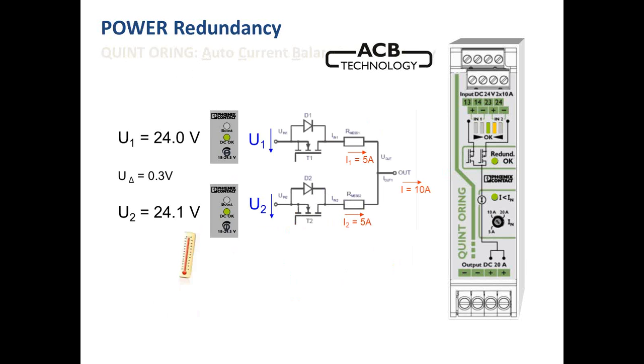O-ring modules also provide something called automatic current balancing, or ACB functionality. Over time, it's normal for a DC output from a power supply to drift due to temperature. A drift will cause an imbalance, and one power supply will provide all the current, and its internal temperature will raise approximately 10 degrees C. 10 degrees C is the key number. At this raise in temperature, it will cut the life of the power supply in half. The O-ring module is able to control the MOSFETs and force even current draw from both power supplies, even though they have drifted. Once the limitations of the ACB has been reached, the O-ring module will alarm.